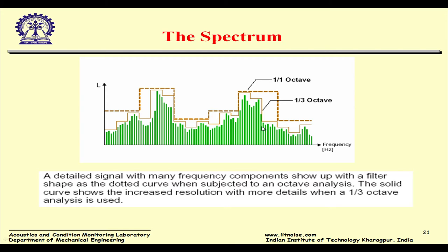Many regulations and regulatory standards mention how I should report my results. Is it 1/3? Is it 1 octave? Is it narrow band? Particularly for machinery diagnostics, we use a very fine narrow band frequency. But for acoustics, 1/3 octave is fine enough, provided we have the other things happening known to us as well.